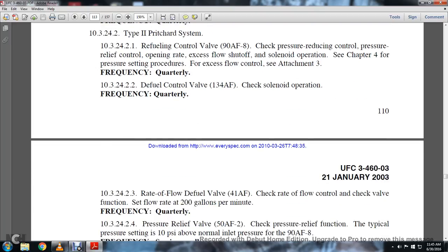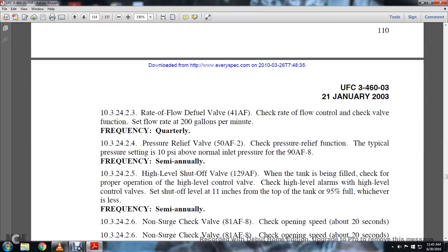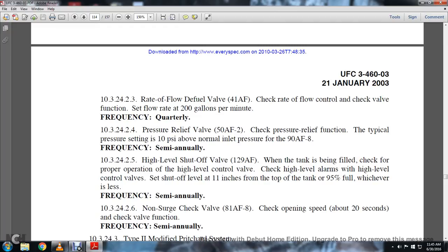The rate of flow defuel valve, the 41 AF model: check the rate of flow control. Check valve function and set the flow for 200 gallons per minute. Frequency quarterly. Alright, the pressure relief valve: check the pressure relief function. Typically, it relieves at more than 10 psi above the normal inlet pressure of the 90 AF8. Frequency semi-annually.